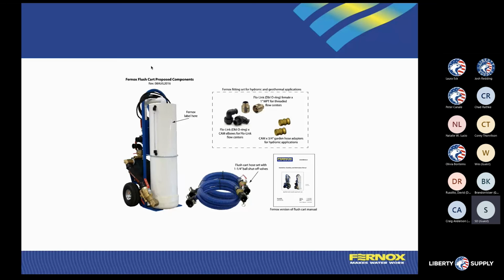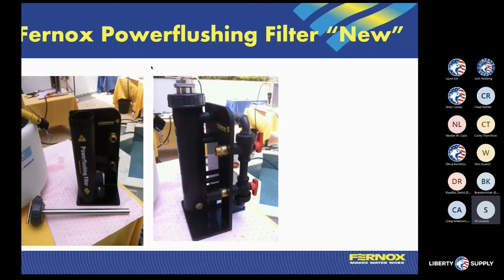We also go counterflow, which means I have a valve on this cart that will not only go in the normal flow pattern, but it'll go in reverse flow. So you can get into any sediment patterns or pickup patterns from that standpoint. So those are another option for flushing with that system. We also have tools that we can add on, like a magnetic filter that we can put in while we're doing the power flush. So this is bigger than a standard residential, but a little smaller than a commercial. So that gives you an idea of what that looks like.